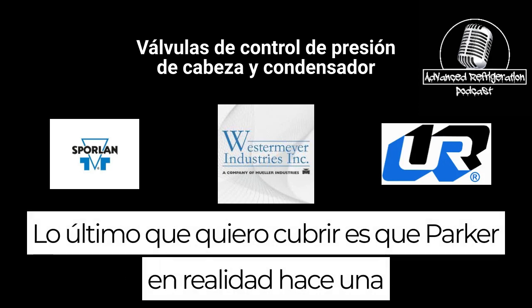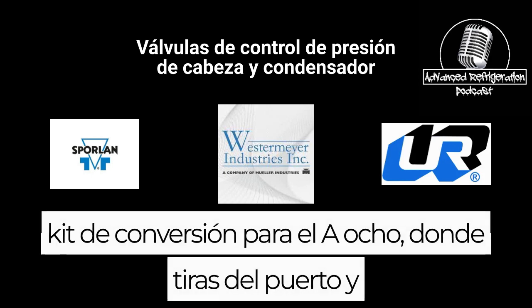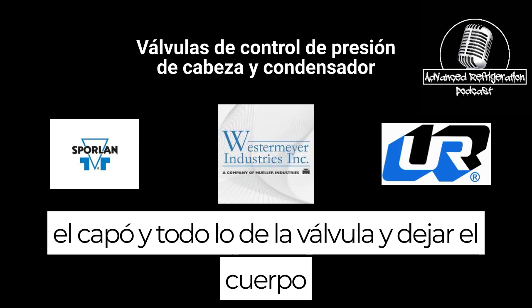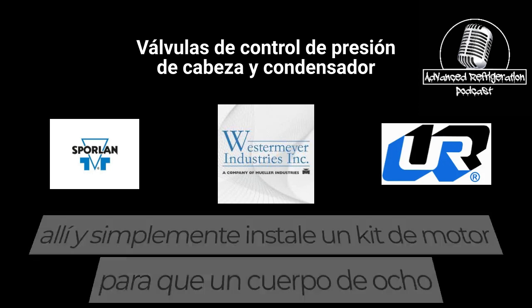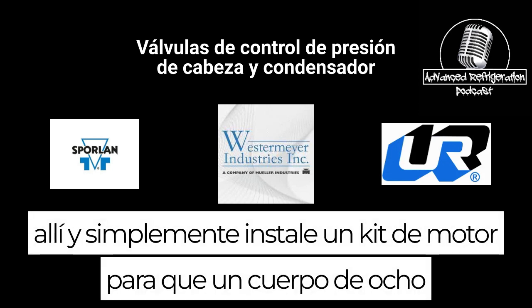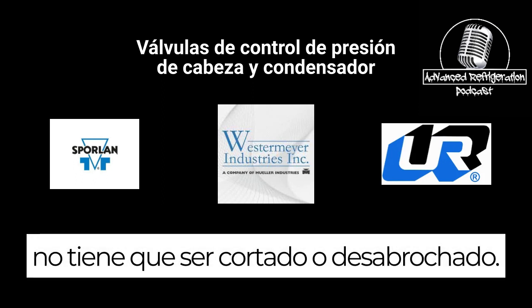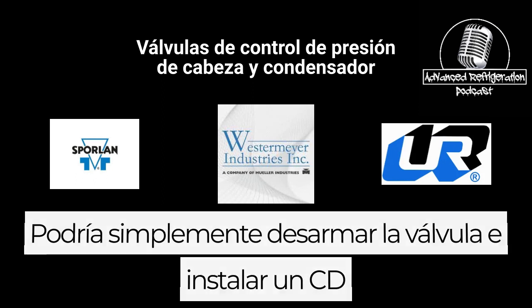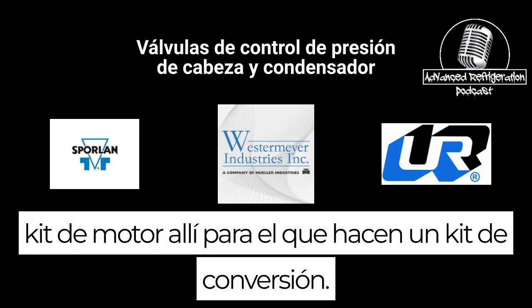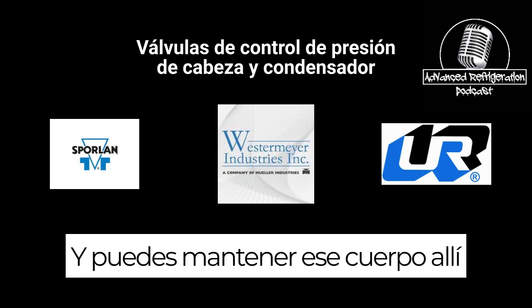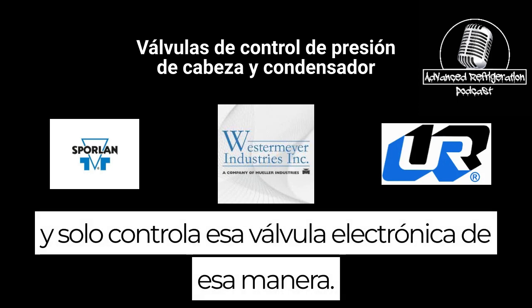The last thing to cover is Parker actually makes a conversion kit for the A8s where you pull the port and the bonnet and everything out of the valve and leave the body there and just install a motor kit. So that A8 body doesn't have to be cut out or unbrazed. You could just take the valve apart and install a CDS motor kit on there that they make a conversion kit for, and you can keep that body in there and just control that electronic valve that way.